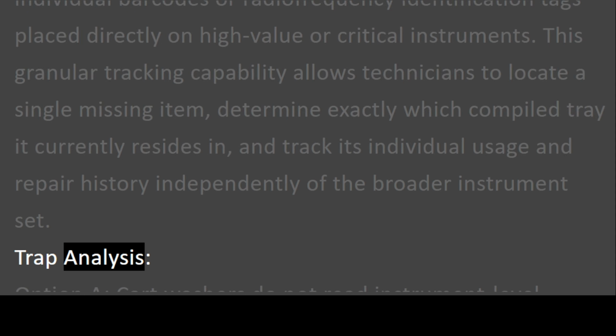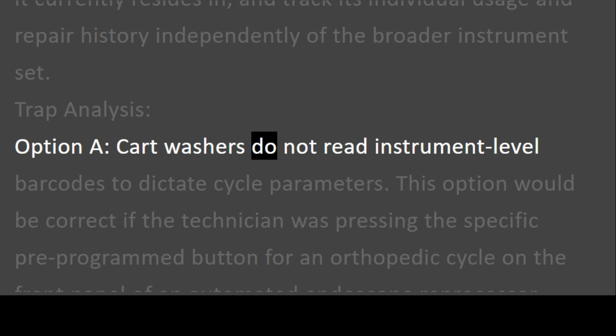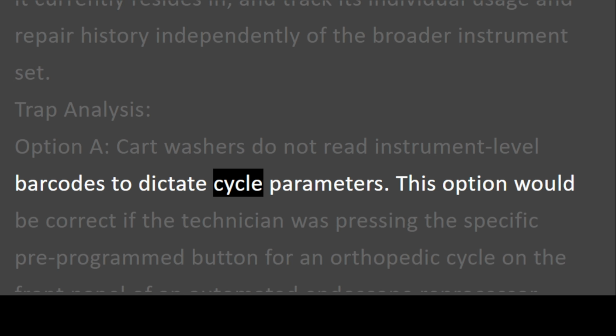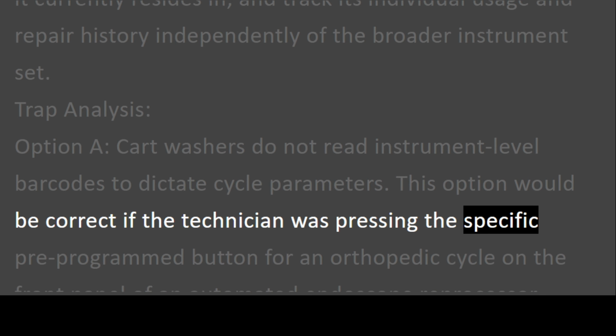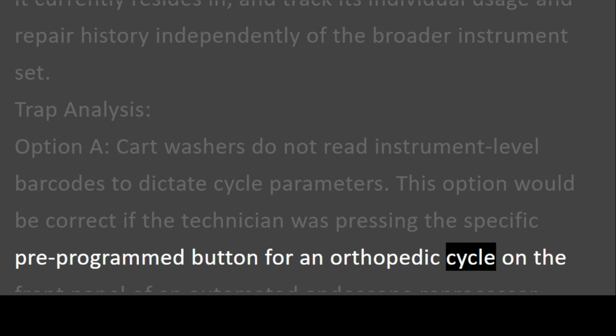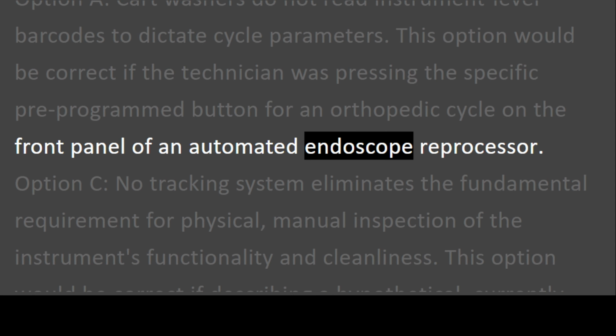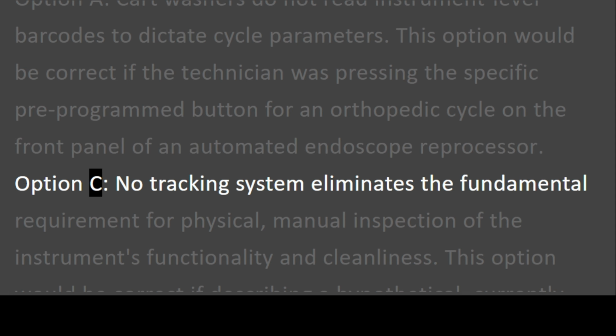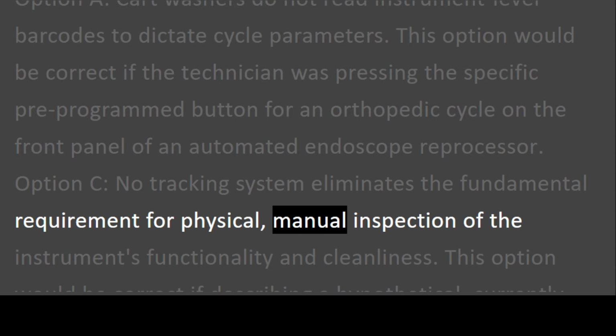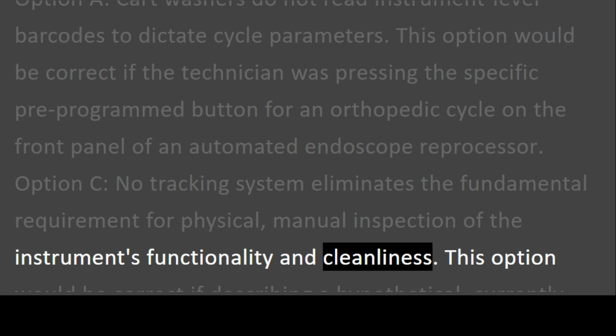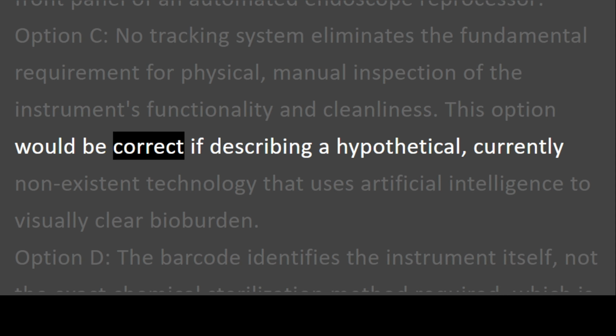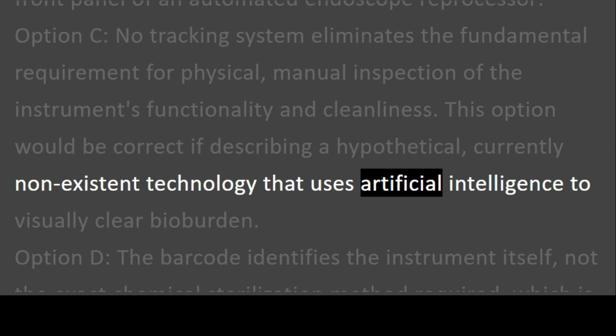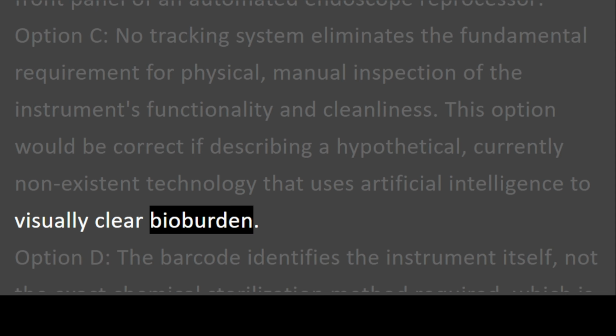Trap analysis. Option A. Cart washers do not read instrument-level barcodes to dictate cycle parameters. This option would be correct if the technician was pressing the specific pre-programmed button for an orthopedic cycle on the front panel of an automated endoscope reprocessor. Option C. No tracking system eliminates the fundamental requirement for physical, manual inspection of the instrument's functionality and cleanliness. This option would be correct if describing a hypothetical, currently non-existent technology that uses artificial intelligence to visually clear bioburden.